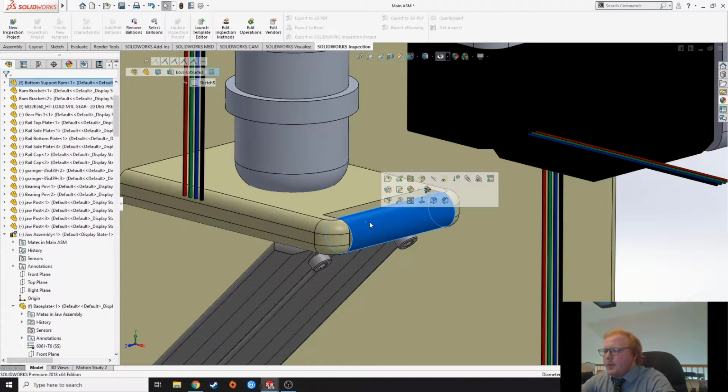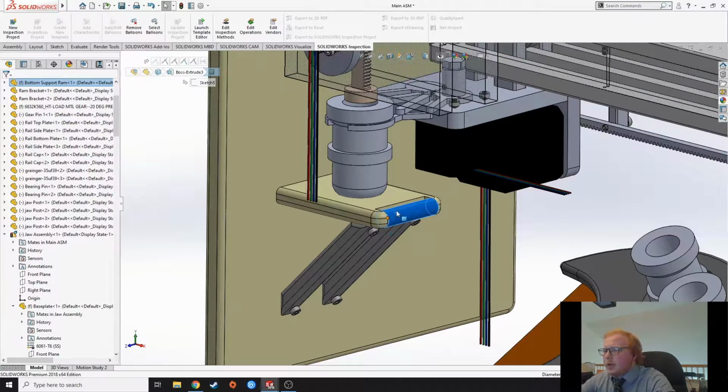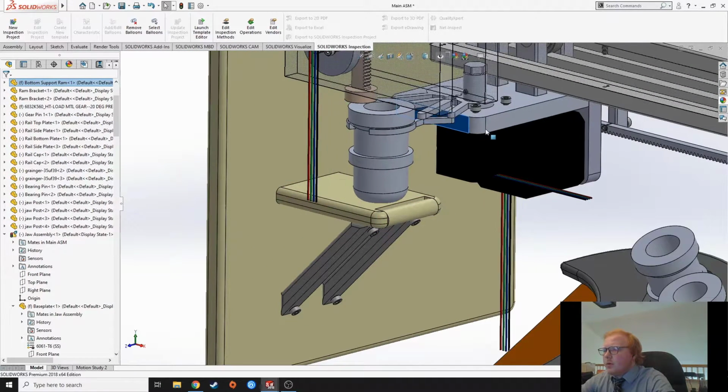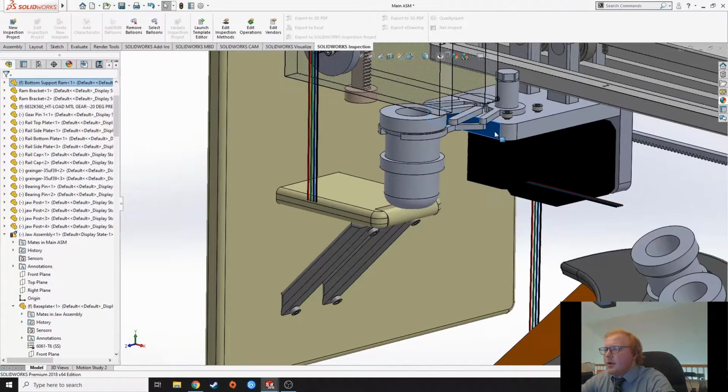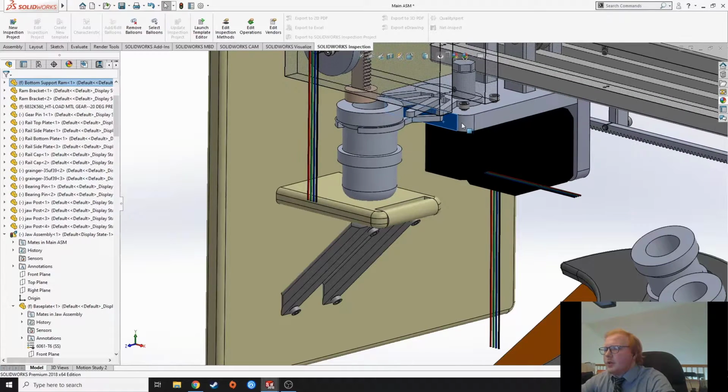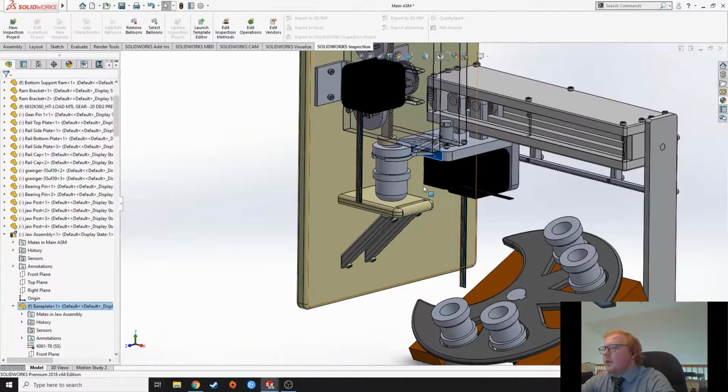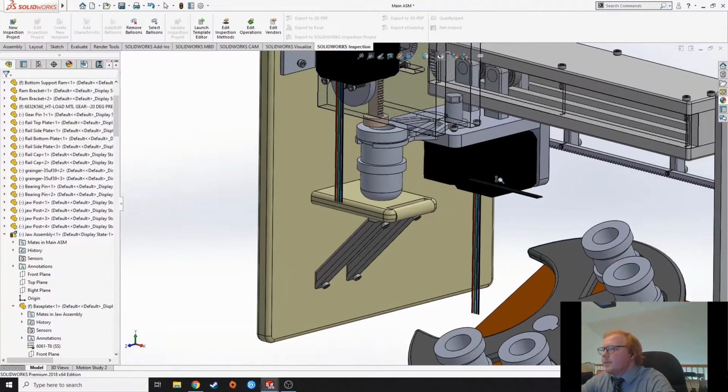There was also going to be a rotating component here to allow for a very smooth transition from the sample container up onto the platform, which then the gripper's jaws would open up so that there wasn't unnecessary force being put on the gripper jaw assembly while it was in testing.